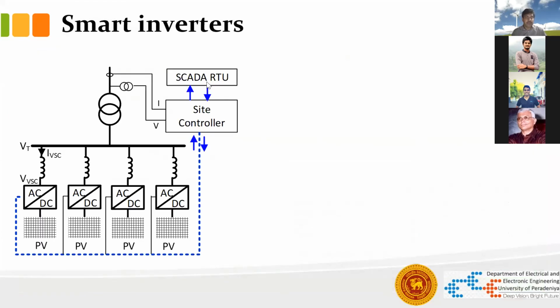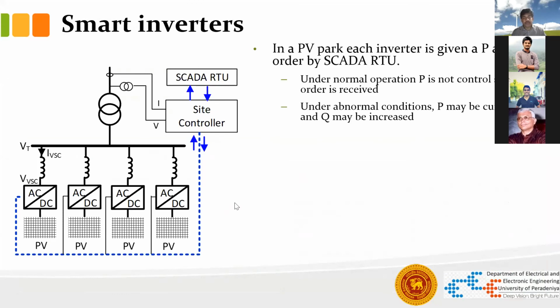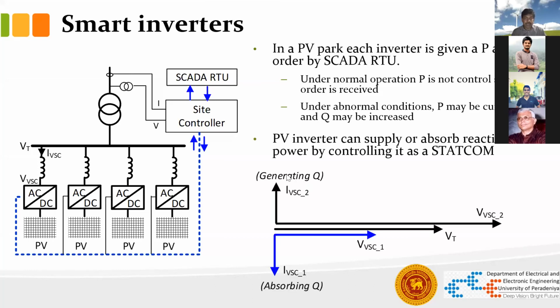What normally happens is your SCADA RTU will receive messages from somewhere asking for reactive power support, from the system controller or from the local controller. Then there is a site controller which will dispatch that message to every PV, and the PVs will then provide the reactive power. These site controllers can also ask for curtailment of the PV, so reactive power control and curtailment. Remember, this inverter and this inductor can act as a STATCOM, static var compensator, providing both absorbing and generating reactive power.